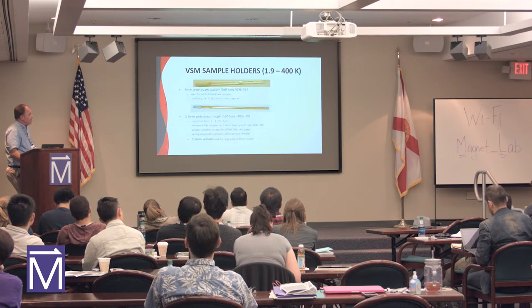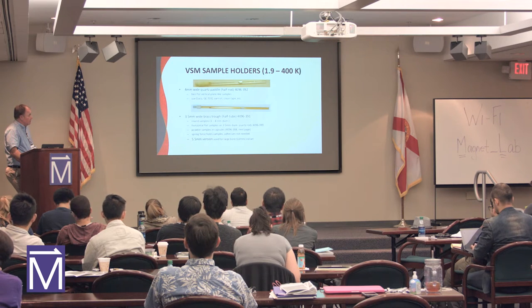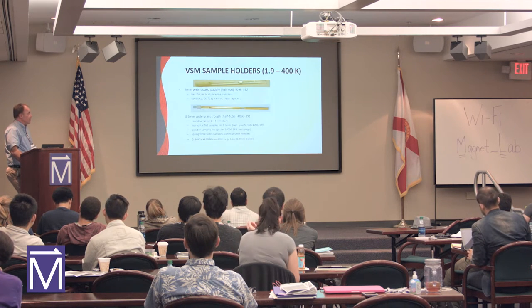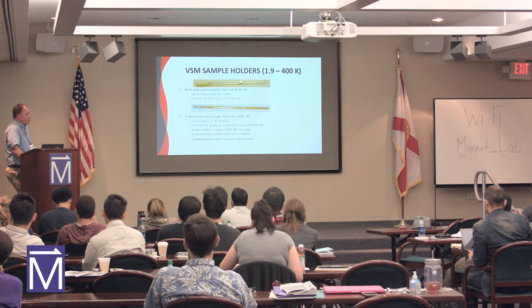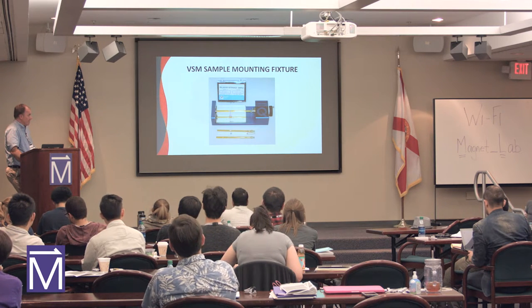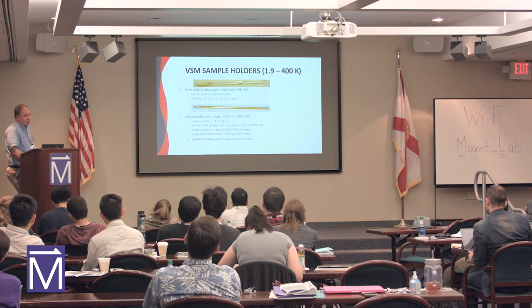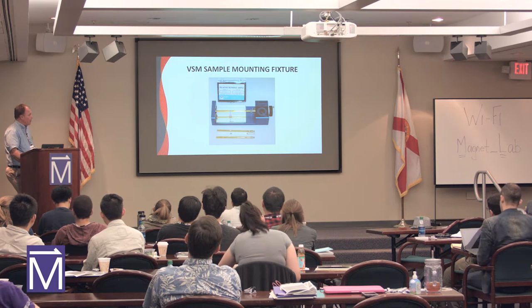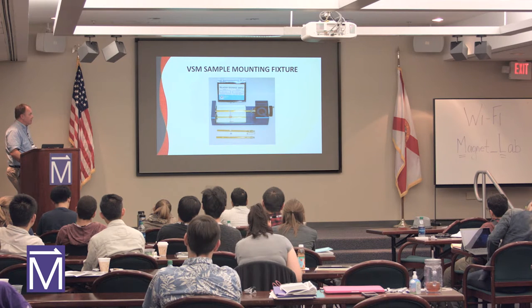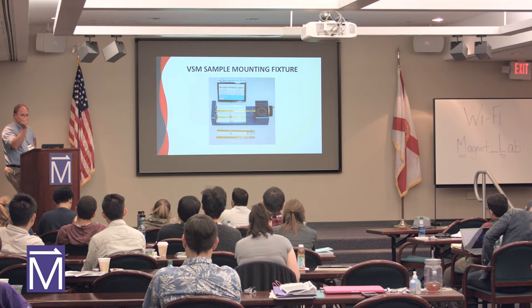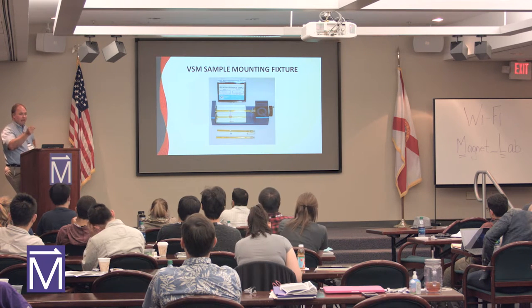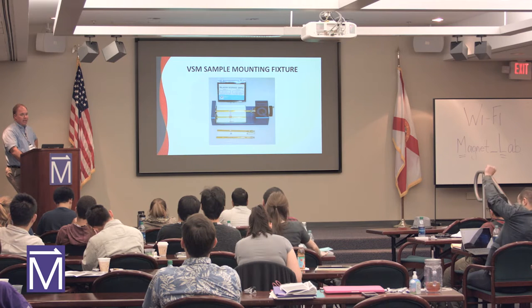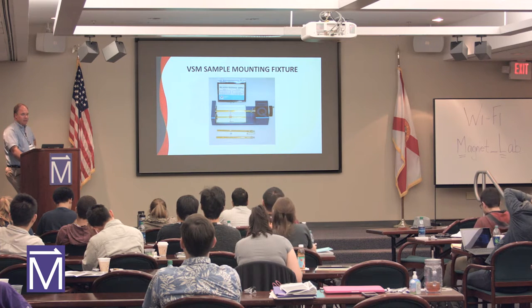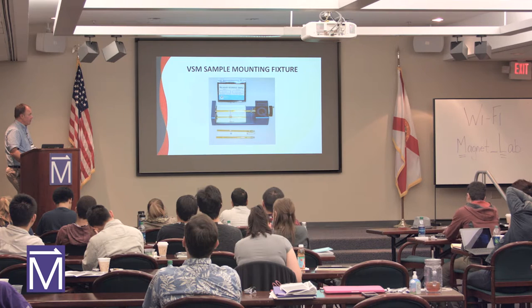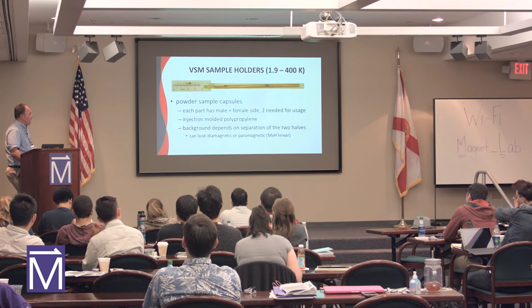We've got a little mounting jig. So on these two holders, you know where the sample location is in the center. Especially on the quartz paddle, so you can figure out where your center is. We have a little alignment jig that lets you place the sample; we used a tape measure. We know where the field center is. You can mount the sample in the center, and that way you know when you put it in the instrument, it's in the proper location. So we give you a little alignment jig. You'll see this in the lab.